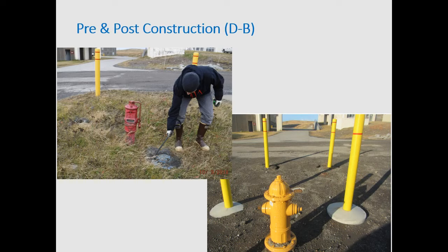Generally the same orientation, looking northwest. We have these post indicator valves out there. We have subsurface valves, so this is a buried valve. When they would say, well, we put all of our valves in vaults, we'd kind of go, are you sure? Where this was, we put a new hydrant and new valving. The water main runs this way, just to give you an idea of what was pre and post.